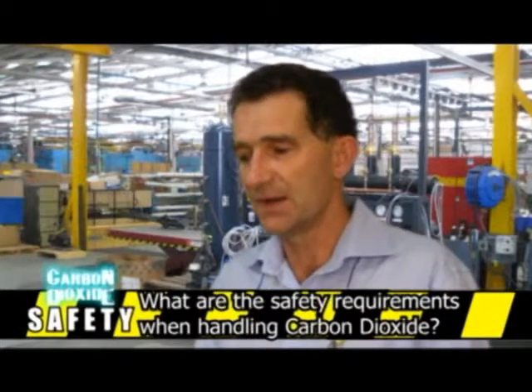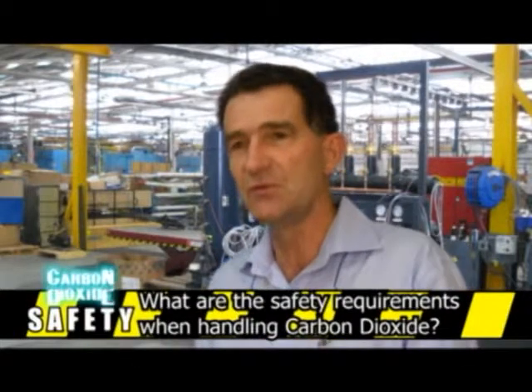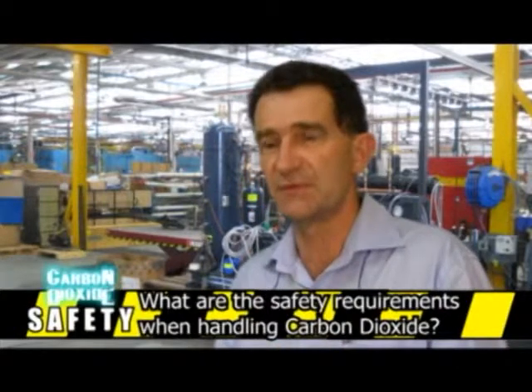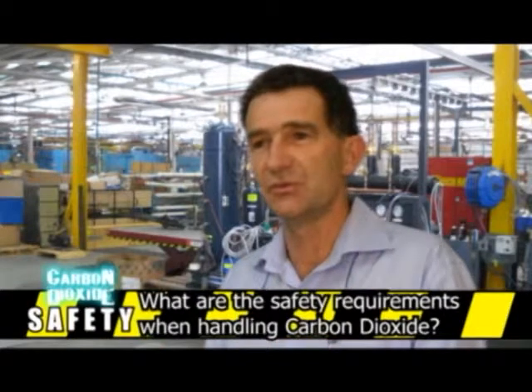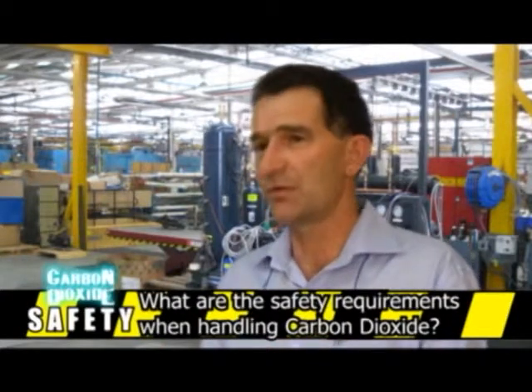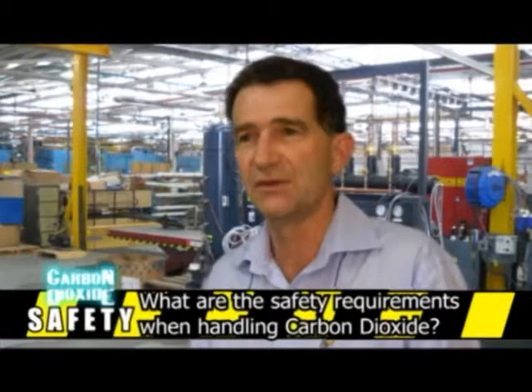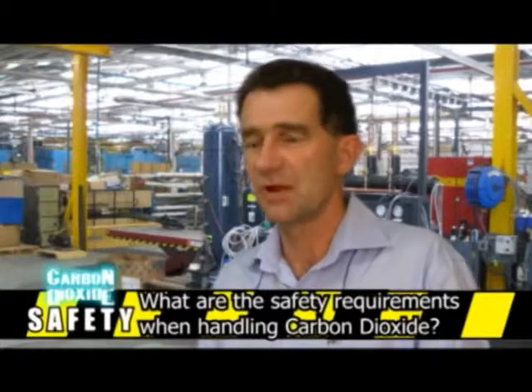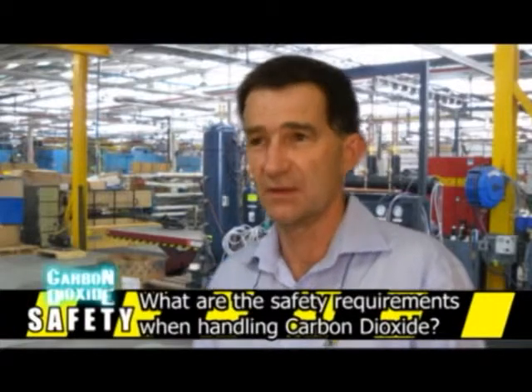And thirdly, you must only use the service hoses and gauges designed specifically for CO2, because it's at much higher pressures than the standard R22 or 404A refrigerants you've used in the past. If you use those gauges and hoses for CO2, you run the risk of the hose bursting and causing injury.